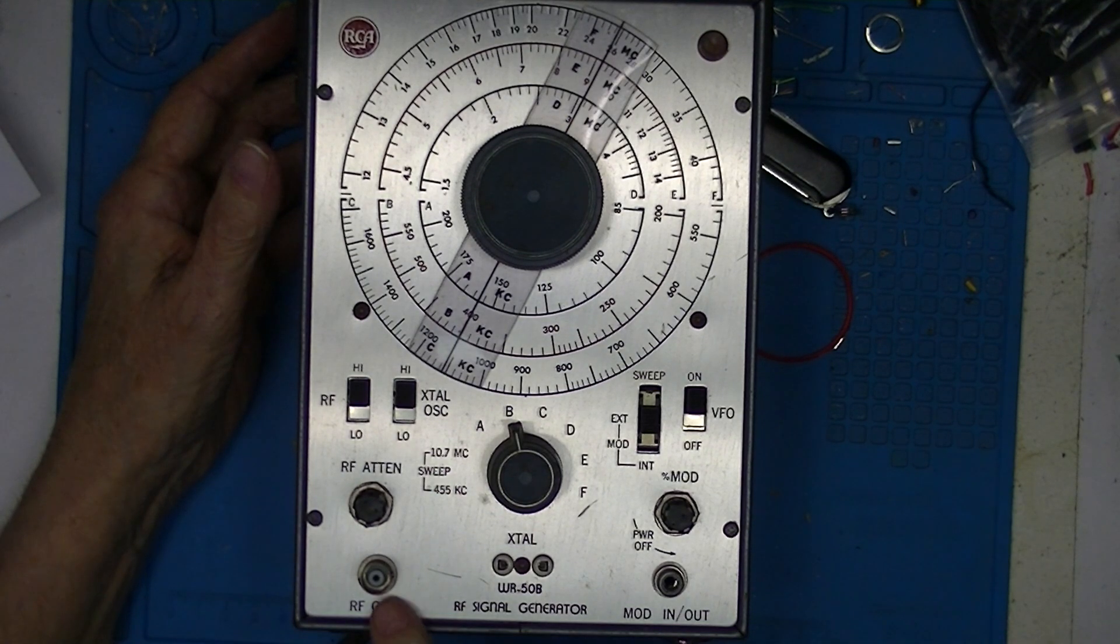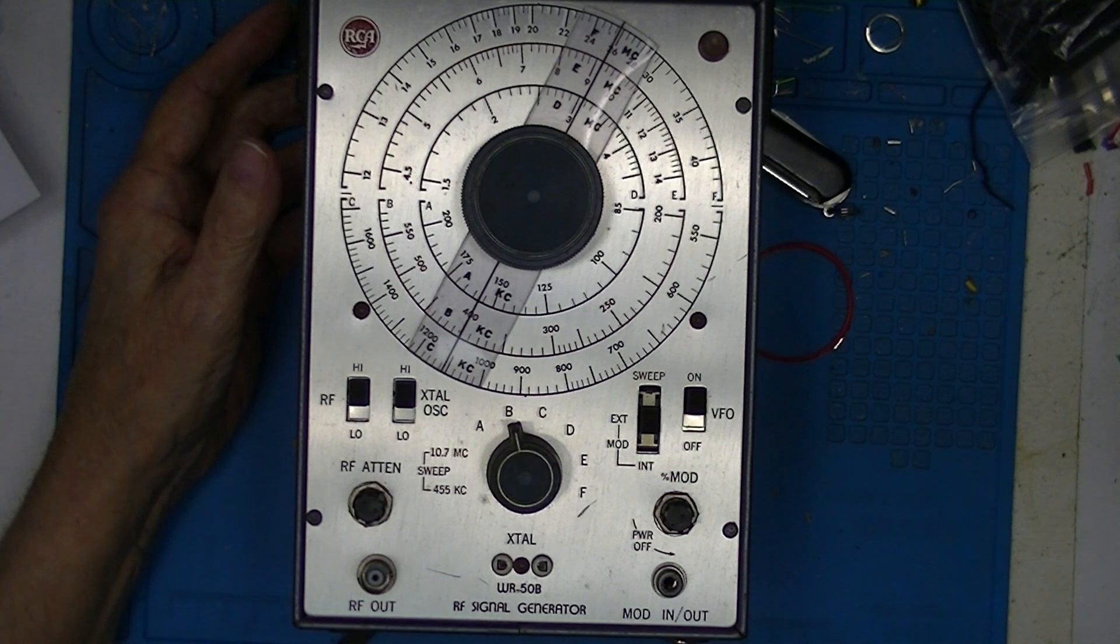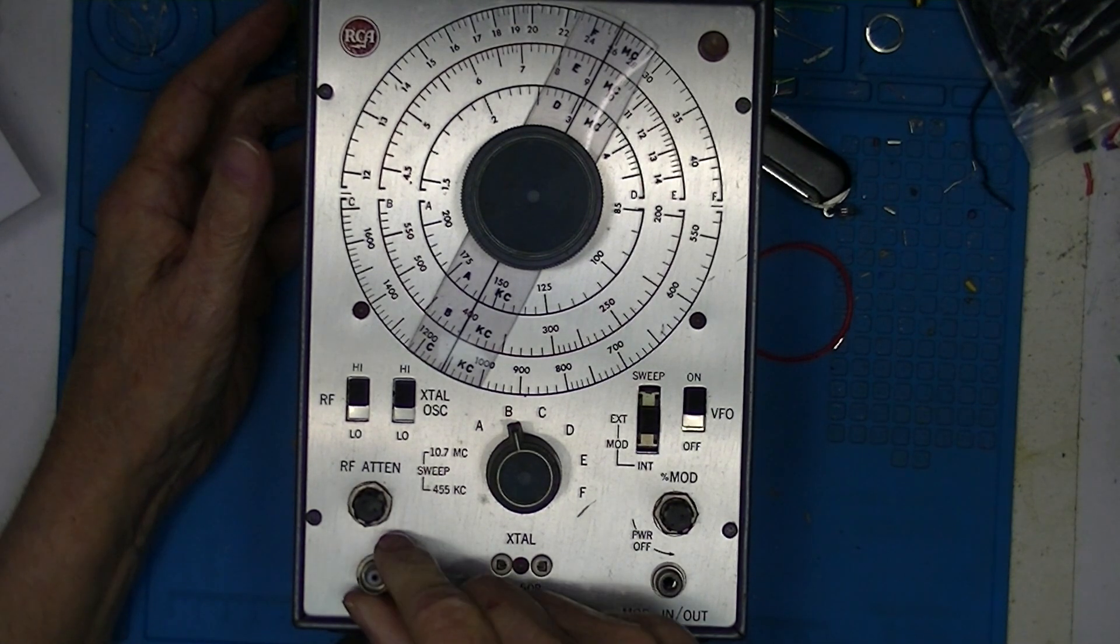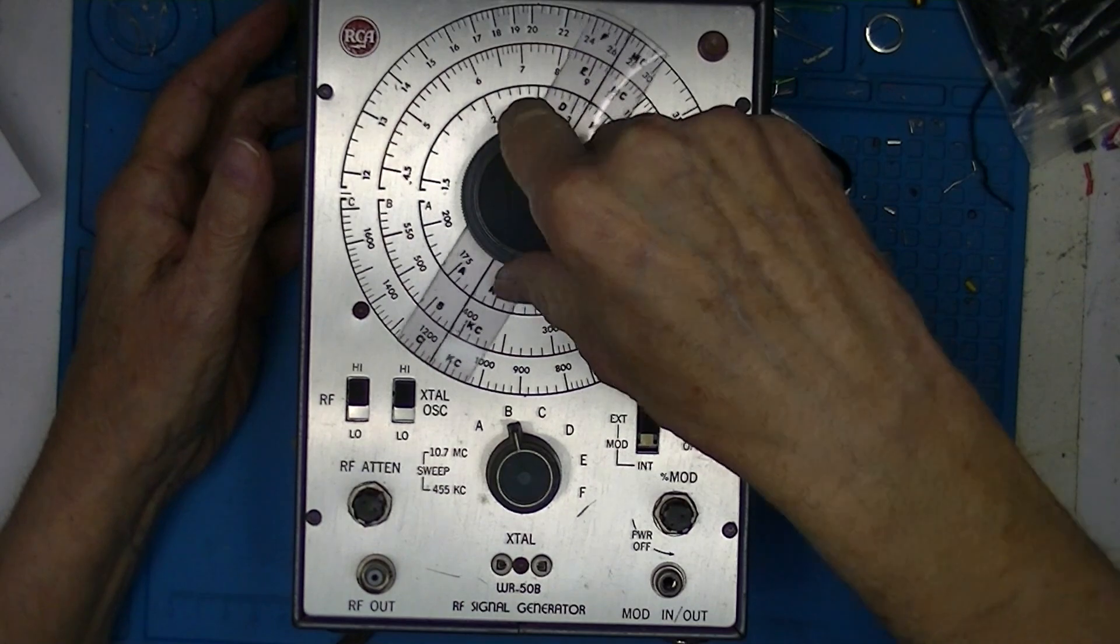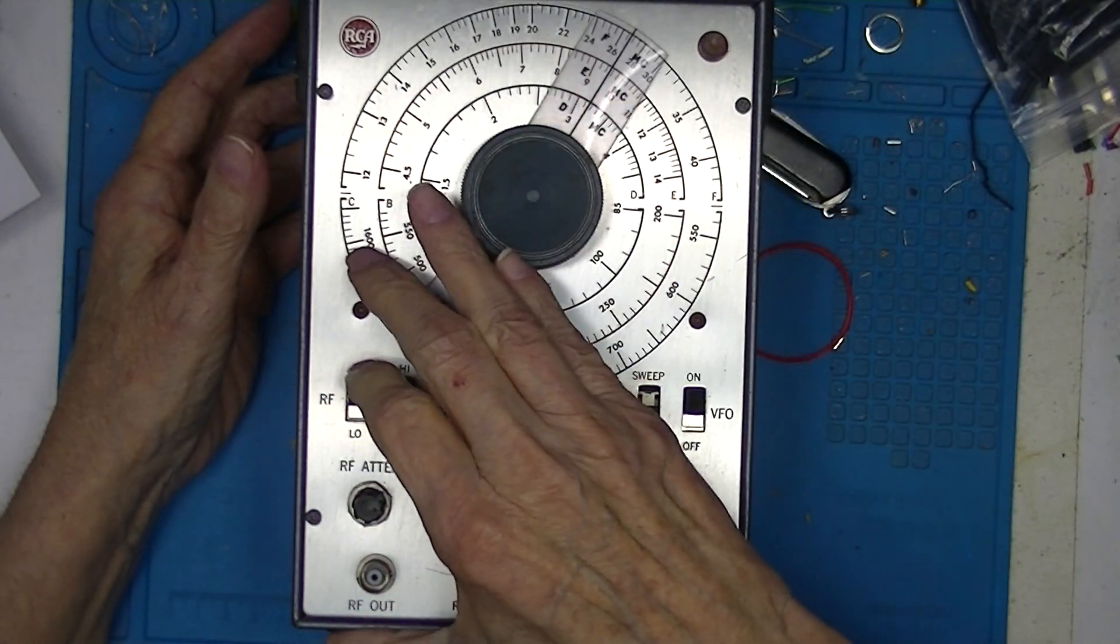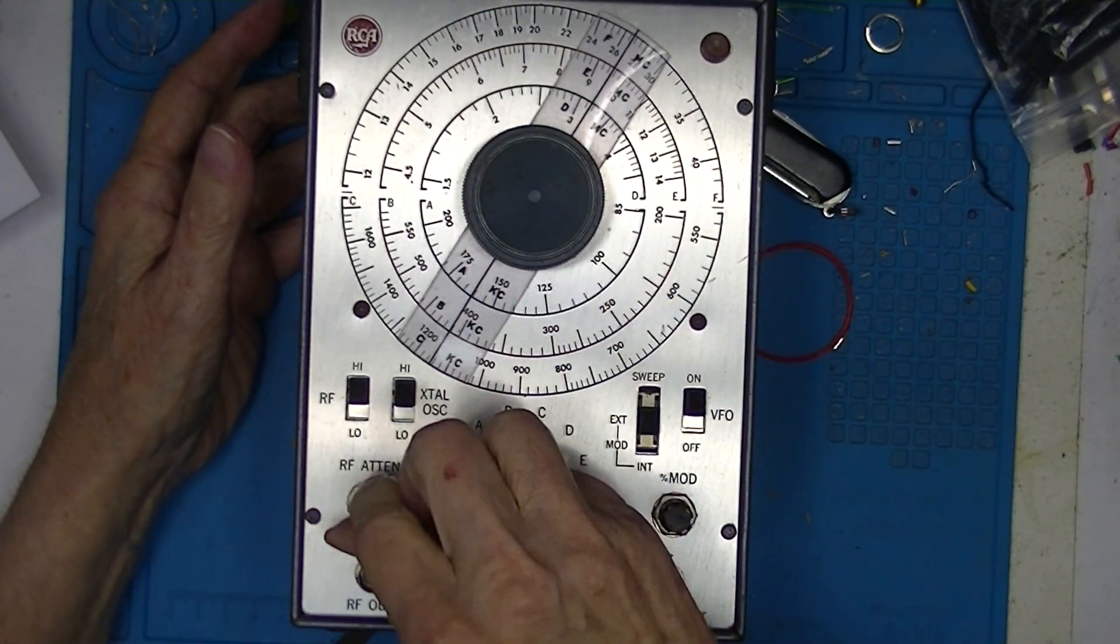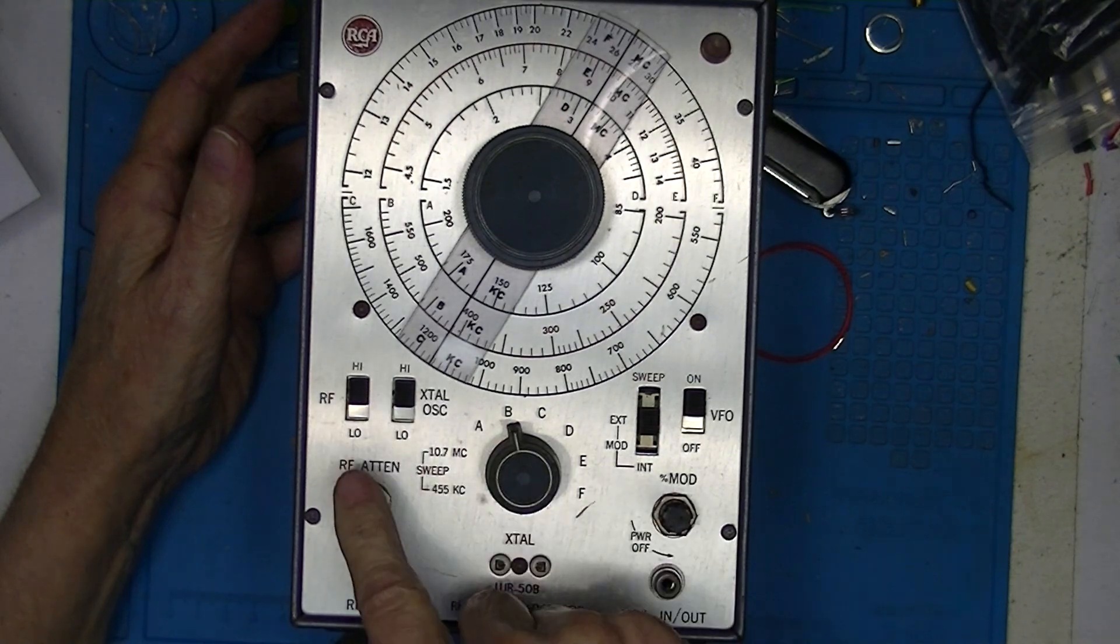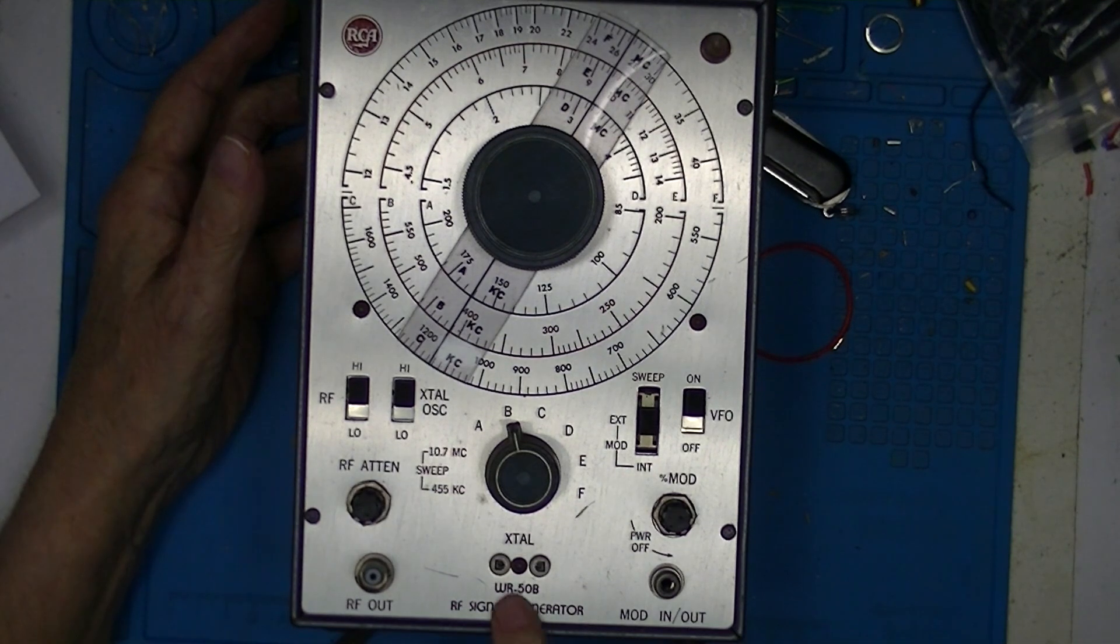This particular one has a BNC connector output. I'm not sure that's standard. I've seen it before but usually these things had a permanently attached coaxial cable coming out of them. In addition to a range switch and a frequency selection switch, we have an RF output high-low switch and a potentiometer for fine RF attenuation.